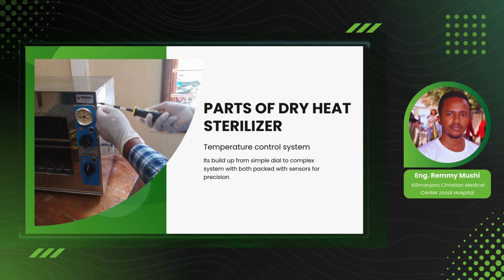The second part is the temperature control. As we can see in this picture, there is a gauge on the top, and beneath the gauge there are two knobs. The temperature control system can be built from a simple dial design up to a complex system packed with sensors for precision of the data acquired inside. With a simple dial, you just select the temperature or the time and start the sterilizer. But in huge machines, the large scale dry heat sterilizers mostly used in industry or in medical settings to sterilize bulk volumes, there may be a much more complex system for control of the temperature.